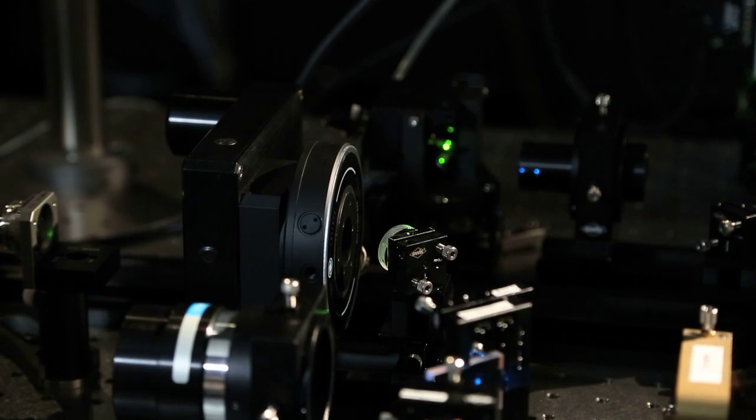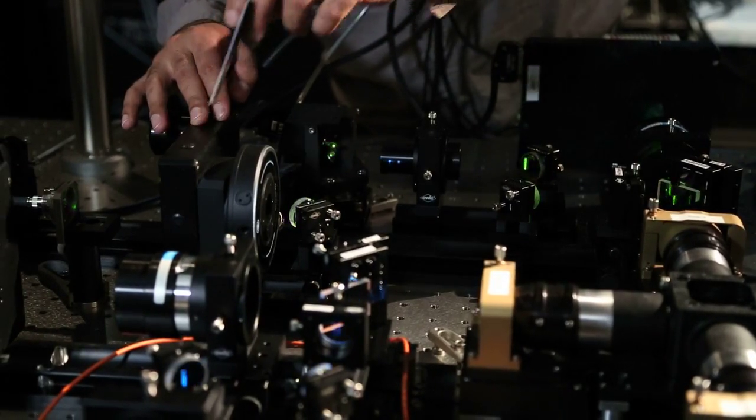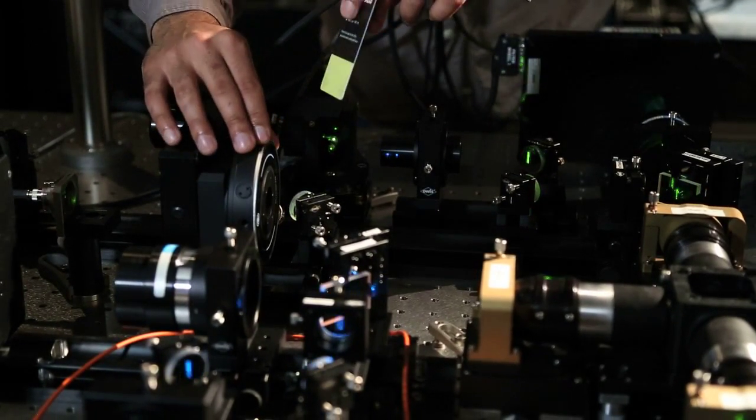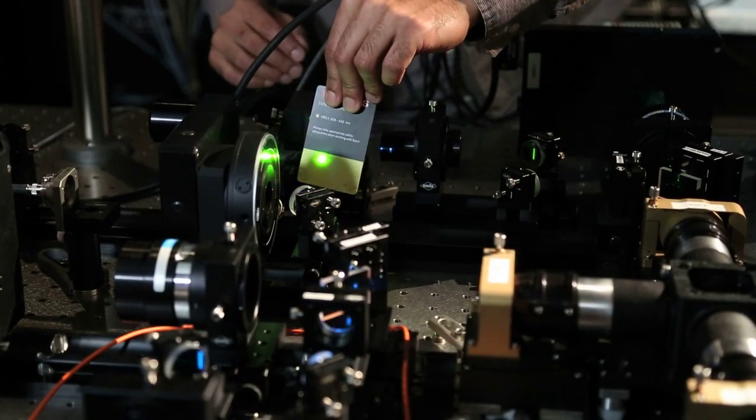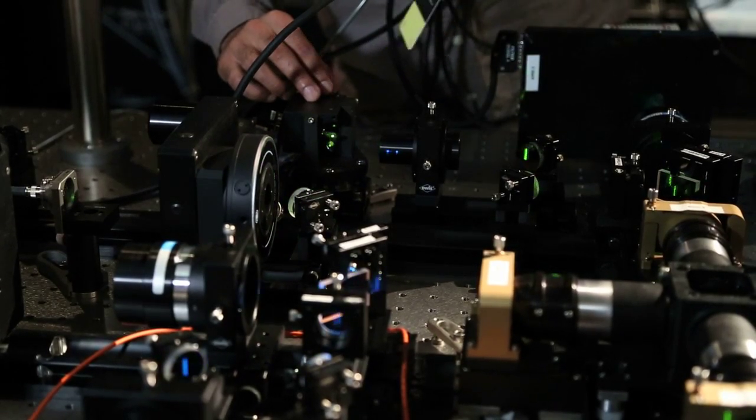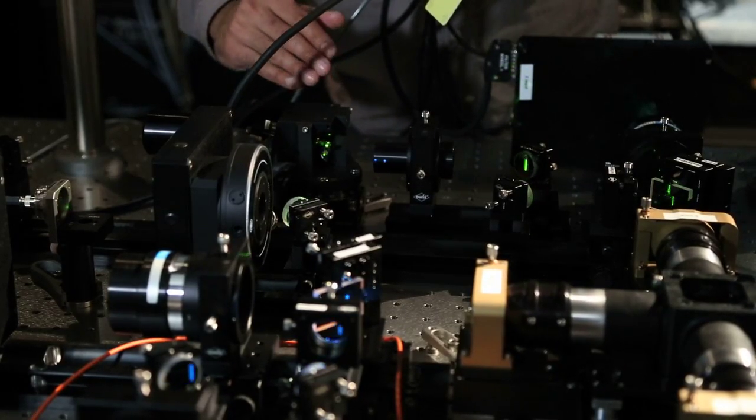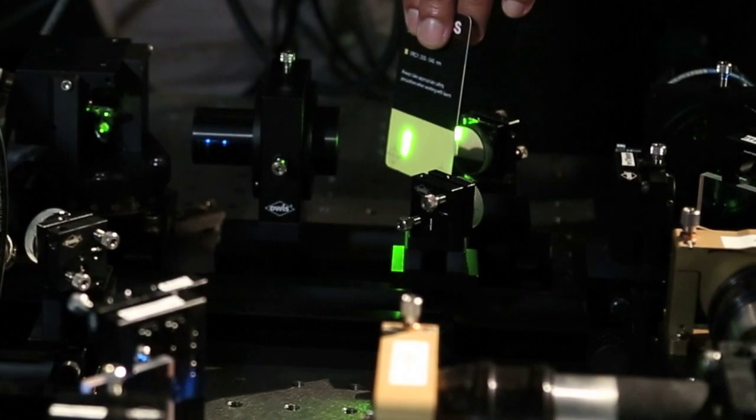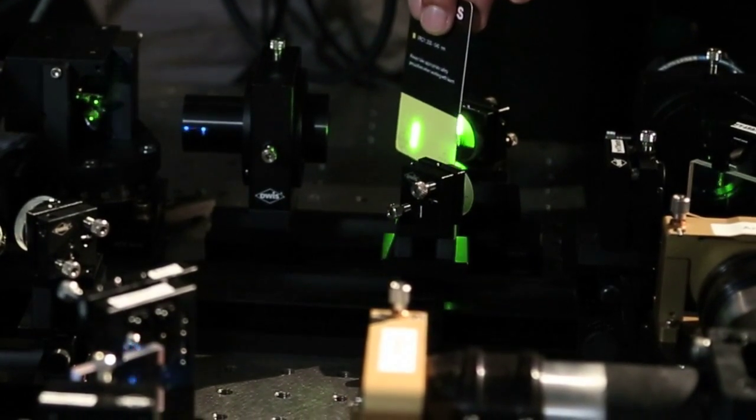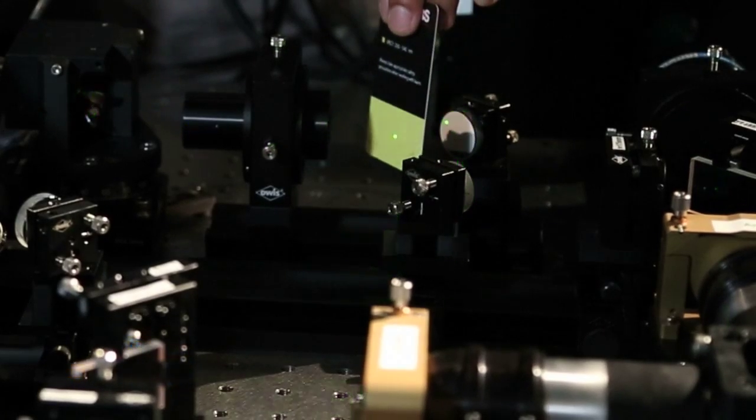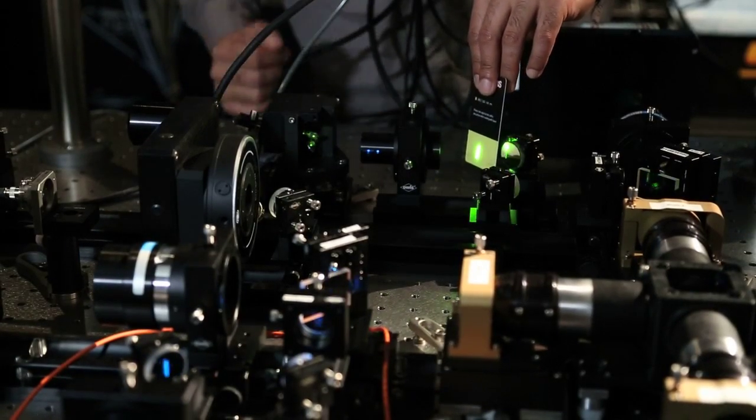Let's go ahead and trace one of the illumination paths here. We have a laser beam coming in and passing through the illumination filter and a shutter. As you can see, this is a Gaussian beam that is now going into the XY Galvo scanner. What this element does is it generates the light sheet. It scans the beam up and down. Once it's done with the up and down scan, it does the lateral scan. It's doing up and down really rapidly, so for our eye it almost looks like a line, and it's doing the sideway lateral scan.